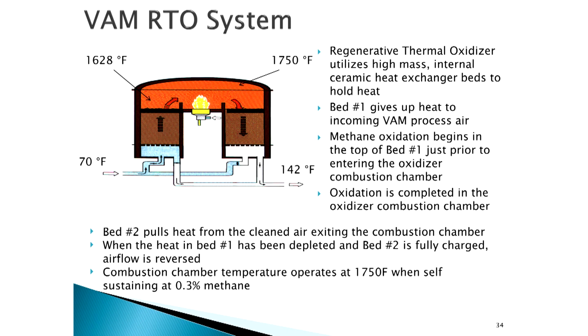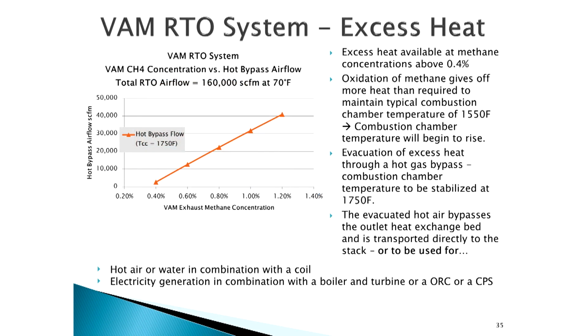But this operates just like the 2-tower that I described to you earlier. And like I said, it self-sustains at 0.3% methane. Here's a little bit of an example of what we do with the excess heat. So if we send it 0.4% or better, we've got extra heat to get rid of. We maintain the combustion chamber temperature at the typical figure that most people are used to seeing in RTOs, 1,550 degrees. And once we send it that 0.4% value, it'll start walking up in temperature on its own.